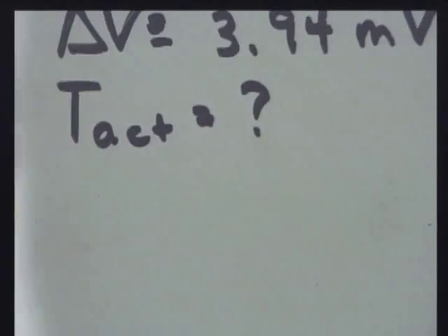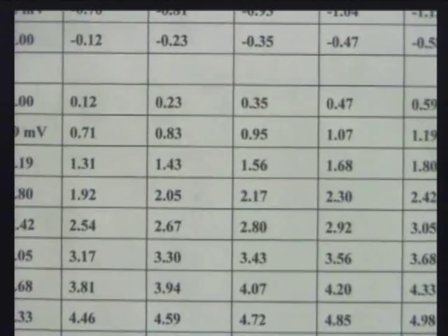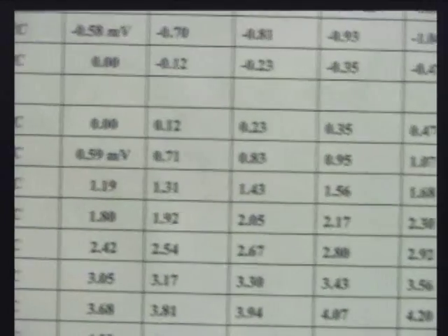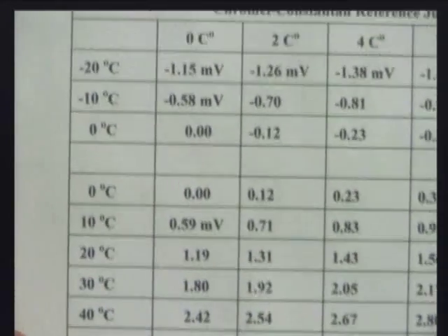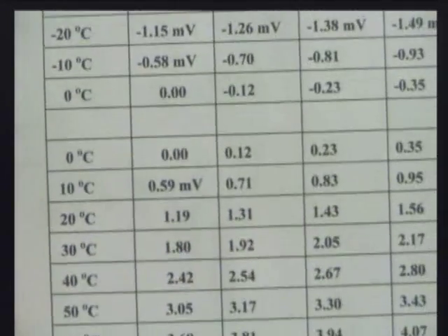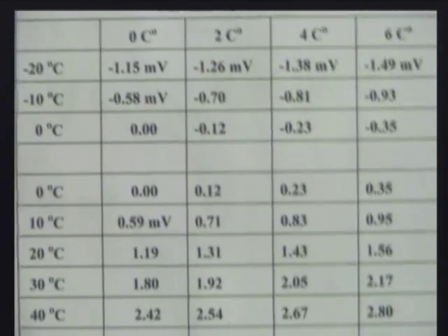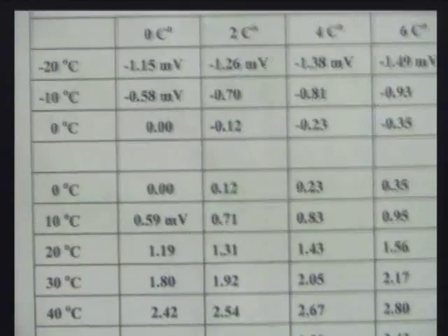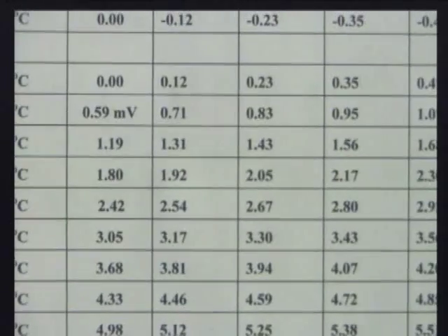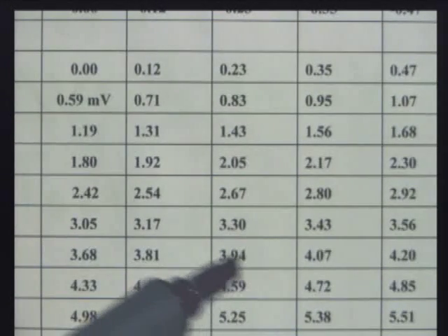I've got 3.94 millivolts. So I look on this chart under millivolts. On the vertical axis on the left, I've got temperature in tens of degrees. Up above, I've got them in two degree increments. So I'm going to look down here in the positive and find 3.94. I made it easy this time. There it is, 3.94 millivolts.